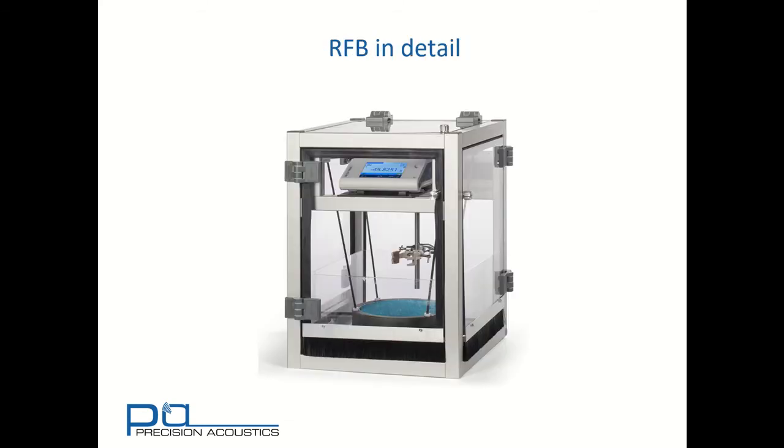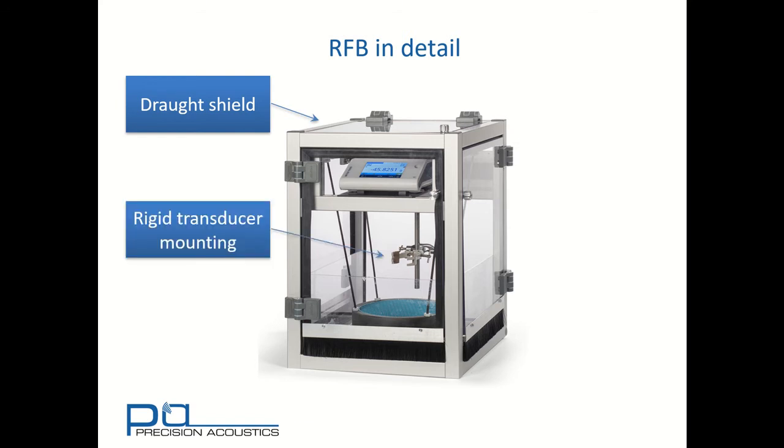Let's look at an RFB in detail. Here we can see a draft shield has been placed around the entire structure. This is to try and minimize the effect of airborne vibration and drafts affecting the measurement components. We also have a rigid transducer mounting to ensure that we've got repeatability and rigidity in the way that the transducer is held over the target. And a large absorbing target is shown here to make sure that we encompass all of the beam radiated from the transducer.